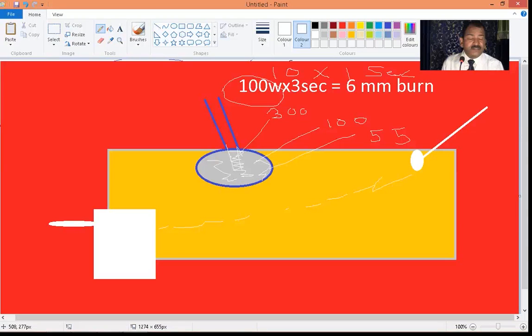So this is the difference between monopolar and bipolar. Collateral injury of the bipolar can be minimized by keeping a very low wattage of the current and using it more intermittently, so altogether collateral injury can be less. But for the same wattage of current it is a little more, because the electrodes are too near and rapid exchange of heat and electrons between the ions creates more collateral injury. Now, the first problem of the bipolar is that for the same wattage of current there is more collateral injury.